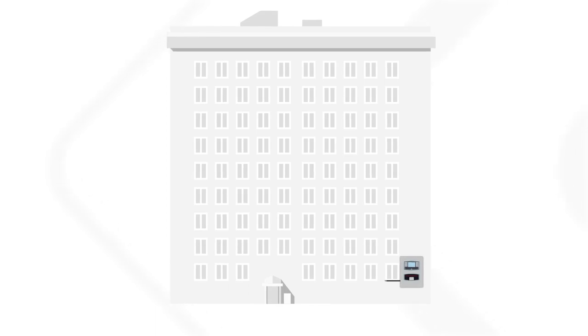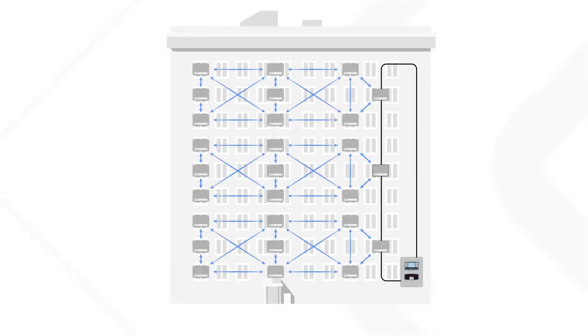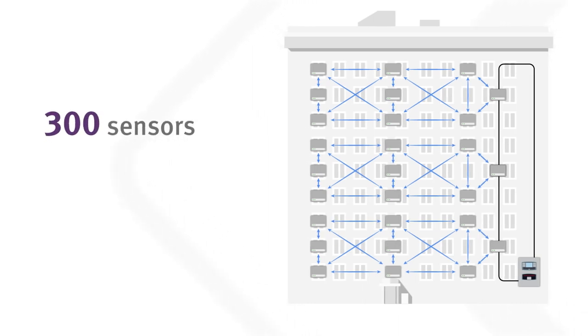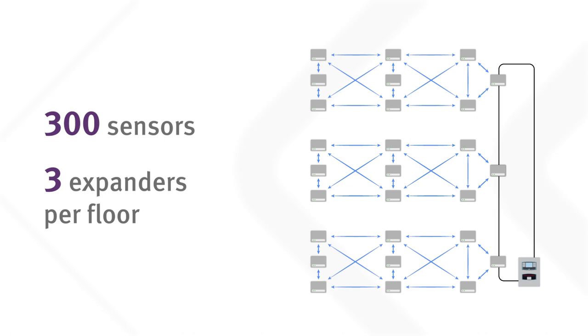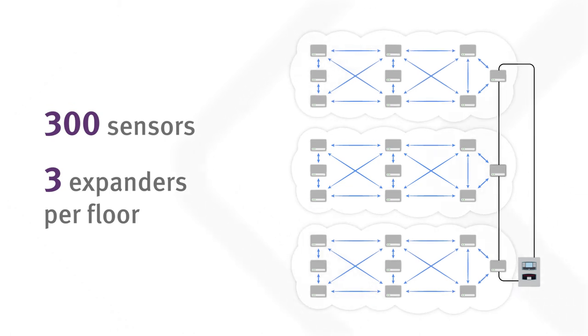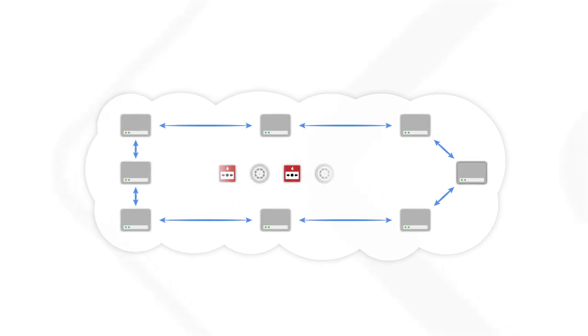To illustrate this point, let's look at a wireless system installed in a nine-storey building. The system contains 300 sensors and three expanders per floor. All devices are divided into three networks controlled by separate translators. This amount of network nodes is sufficient to provide each device with multiple communication paths.